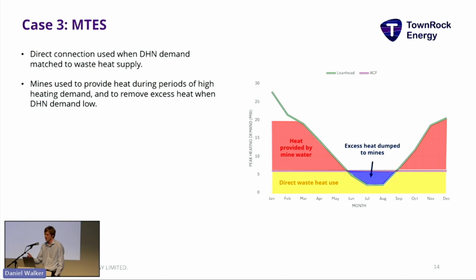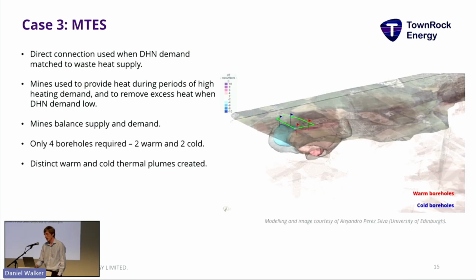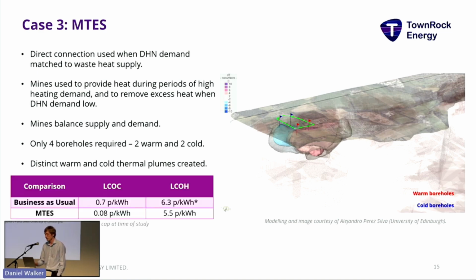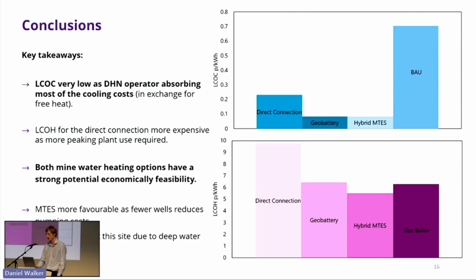In the summer, you don't need to rely on alternative cooling methods - you just dump that heat to the mines. Overall, there's a much better balance of supply and demand, and only a minimal reliance on peaking plant. Because you're using the direct connection when you can, fewer boreholes are required, so lower capex, lower pumping costs, and the result is a levelized cost of heat that's actually more competitive than gas, which is great news.